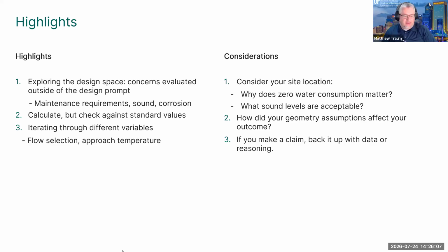While we're talking about crazy out-of-the-box ideas, and I mean you guys must face this all the time, it's humid, right? It's horribly humid, and they're like, why are we doing these wet cooling towers here? It just kills me about UF too. UF has wet cooling towers all over the place, and they're running full bore all summer because the humidity is like 95%. There's very little extra capacity in the air to absorb more water per the psychrometric chart.